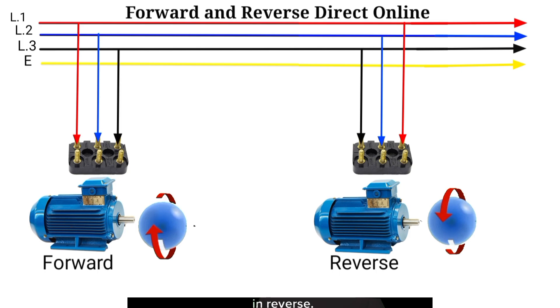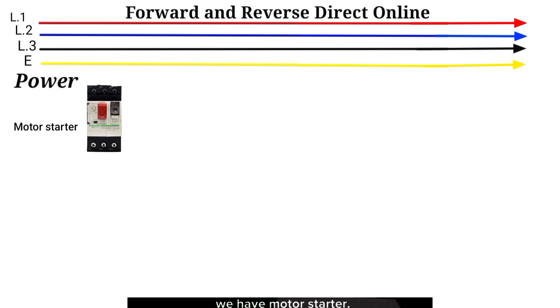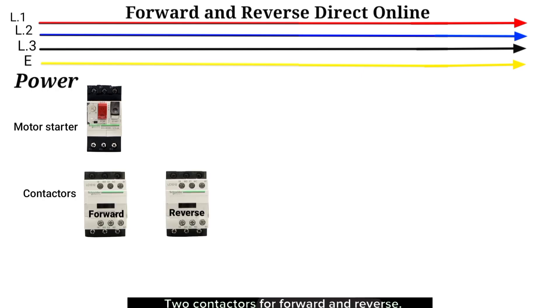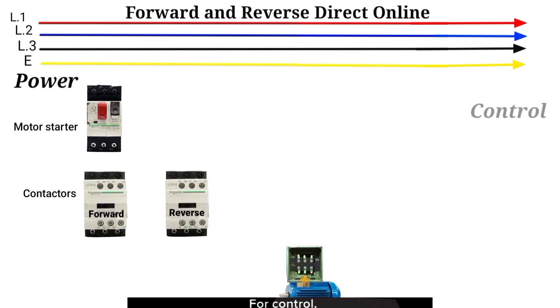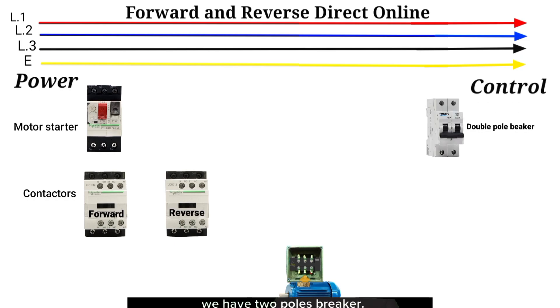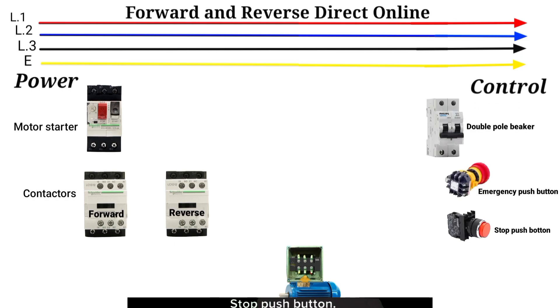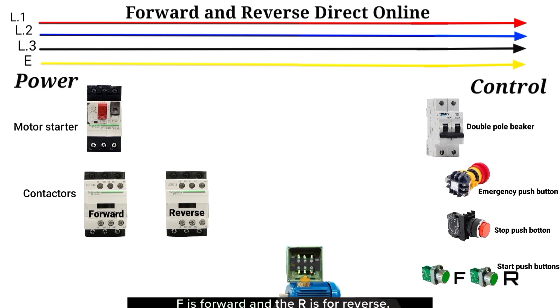Let's dive into the main process. For power, we have a motor starter, two contactors for forward and reverse, and the motor. For control, we have a two-pole breaker, emergency push button, stop push button, and two start push buttons — F for forward and R for reverse.